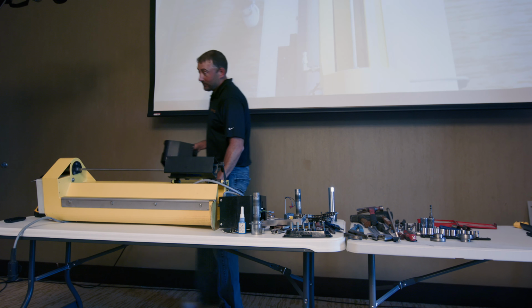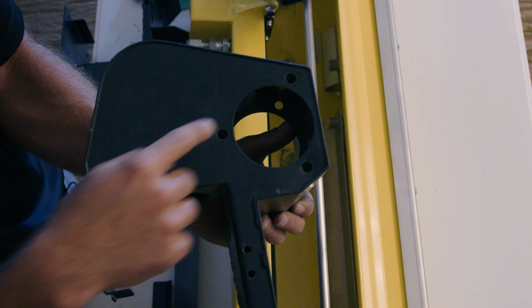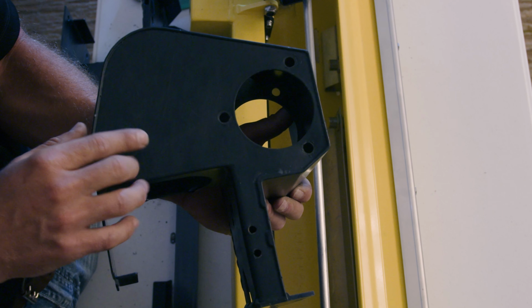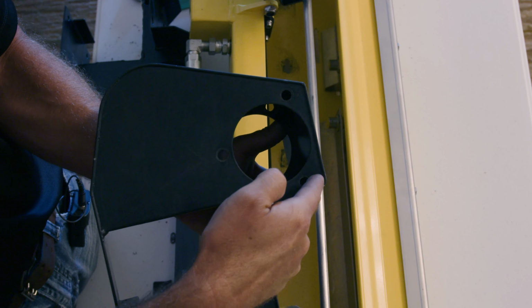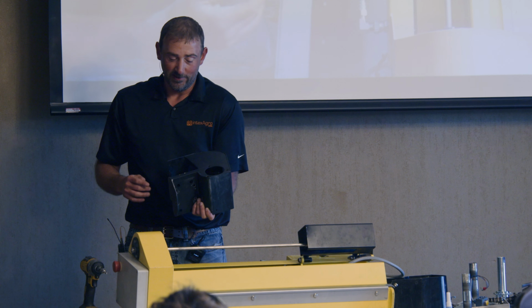Might not be able to see this, but this is the head that breaks. It's always down here. When I took this one apart, all 4 of the set screws on the hub bearings were broke. It breaks that weld, which then tilts your probe in, still runs, but nothing's lined up, ends up catching your bucket, wrecking your tip real fast, and you'll just hear a lot of grinding when the probe comes, or the tip comes through your probe. So just keep an eye on those 4 set screws.